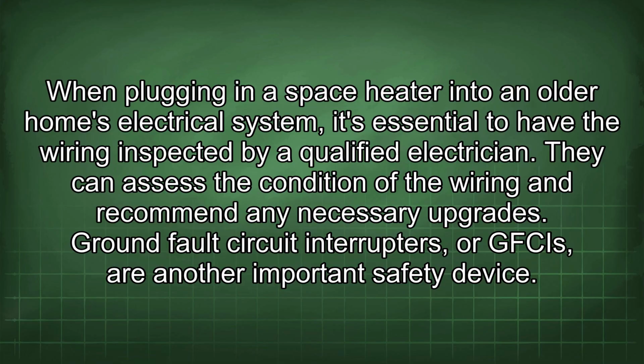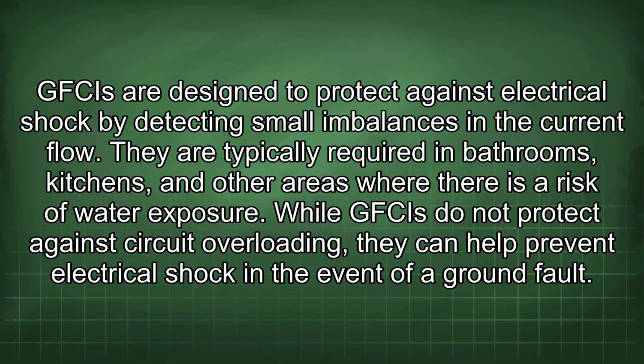Ground fault circuit interrupters, or GFCIs, are another important safety device. GFCIs are designed to protect against electrical shock by detecting small imbalances in current flow. They are typically required in bathrooms, kitchens, and other areas with risk of water exposure. While GFCIs do not protect against circuit overloading, they can help prevent electrical shock in the event of a ground fault.